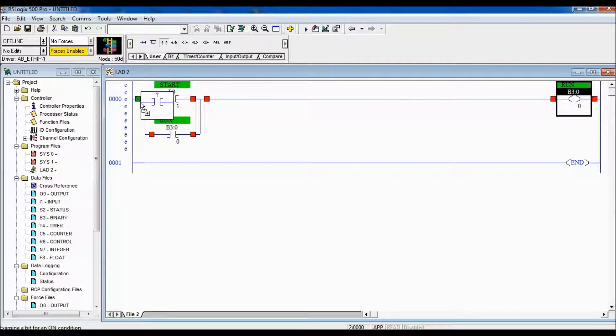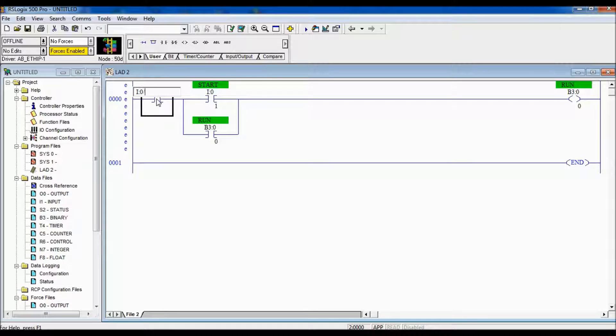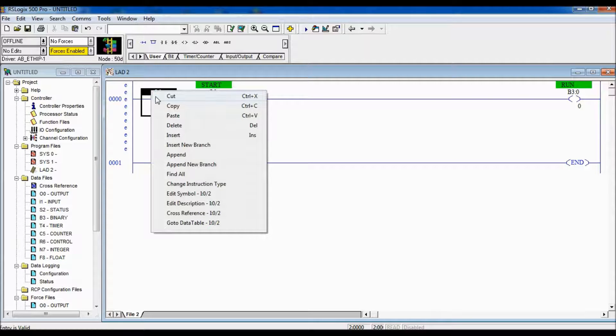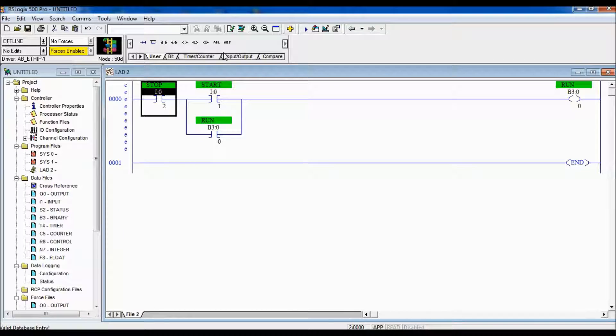The stop push button I'm going to put in here is located at I colon zero slash two and it is wired normally closed. So I want to use examine if closed, and I'm going to call this my stop. So there's our logic for our run bit.